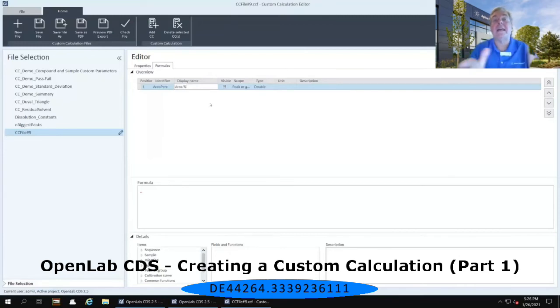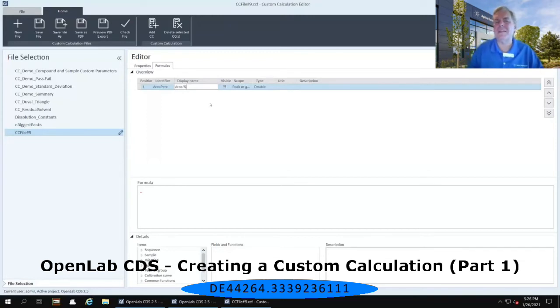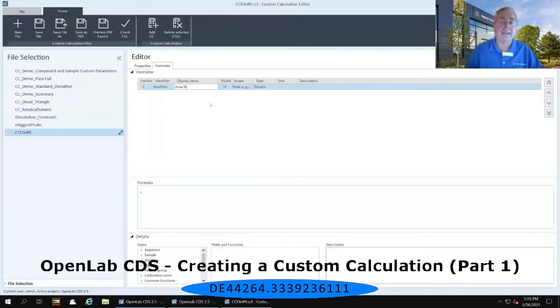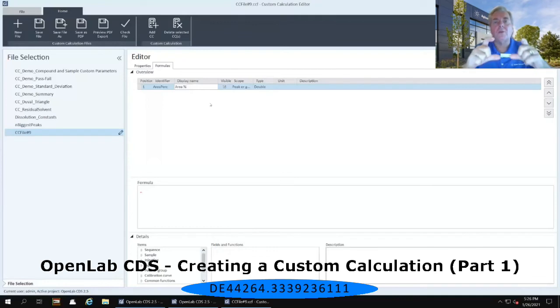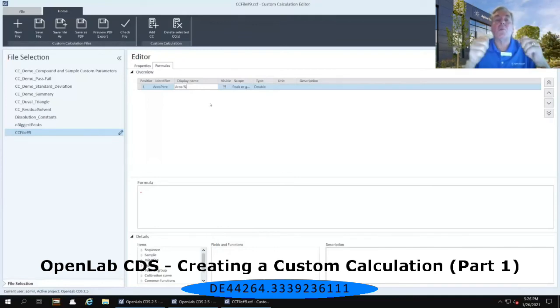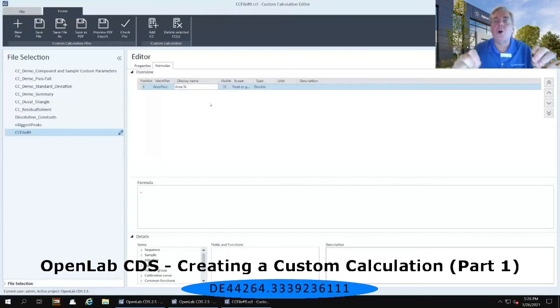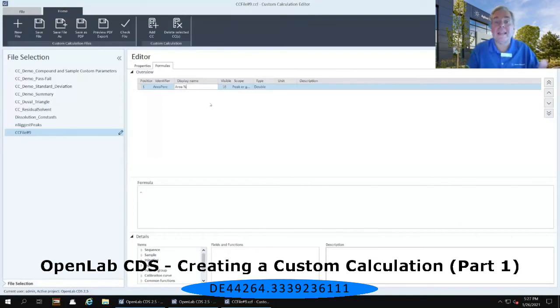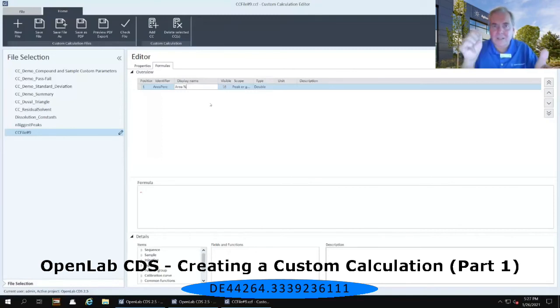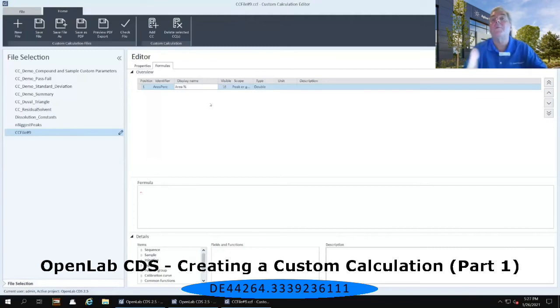Immediately to the right of that, there is a visible tab, and it's currently checked. Now, your next logical question might be, when would I want something to be invisible in a calculation? Well, let's say that I am doing a calculation on a set of data that contains both calibration standards and unknown samples. But I want the calculation to be done on only unknown samples. It doesn't make sense to do them on my calibrators. So, my very first line in my custom calculator could be to query my data and only show me unknown samples. Don't show me my calibrators. But I don't necessarily need to see that in my custom calculation file. So, I can put that in as an instruction in the custom calculator, deselect that visible check mark, and now it will use that as a filter for my data.